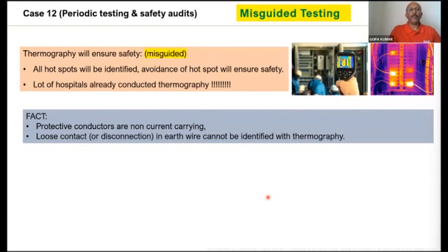In fact, thermography is not a recognized test in the IEC 60364 other than solar PV. For low voltage installation, of course, solar PV, yes, but other than solar PV, thermography is not a recognized test, even in the Indian standard IS 732 or NEC. So by doing thermography, don't expect that you get all safety things.